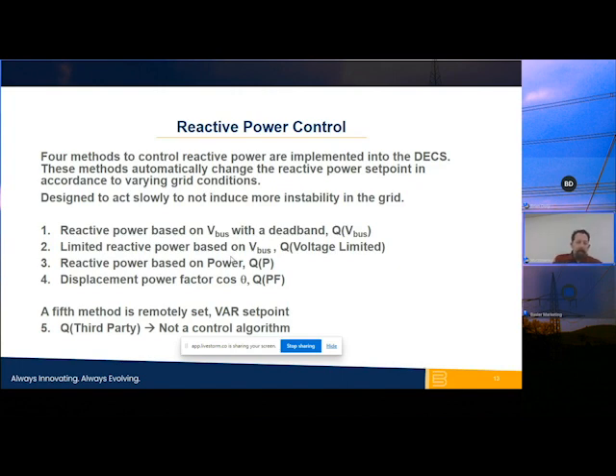And then we have the QP, which is where we control the reactive power based strictly on the power. We're looking at the active power component, and we can plot up to 10 points, creating a graph that says at any particular active power point, I'm going to be at this amount of reactive power. So I can plot a curve of up to 10 points that the voltage regulator will follow to maintain the reactive power component.